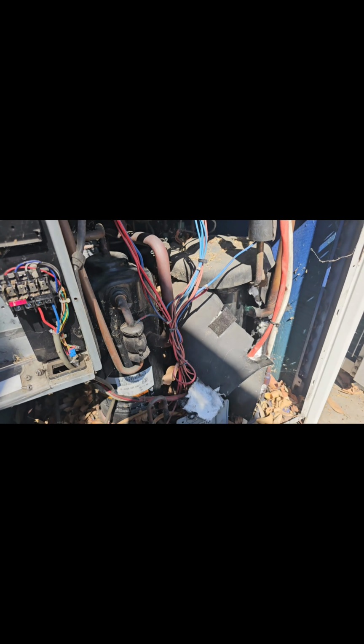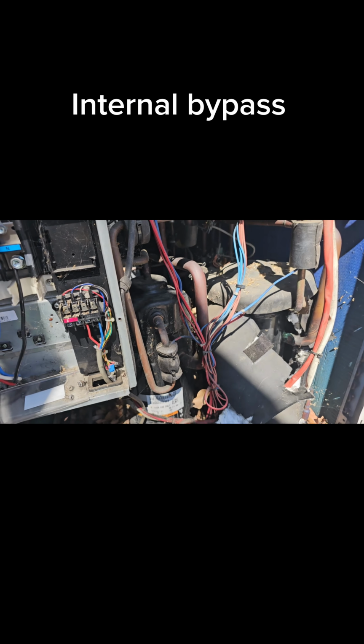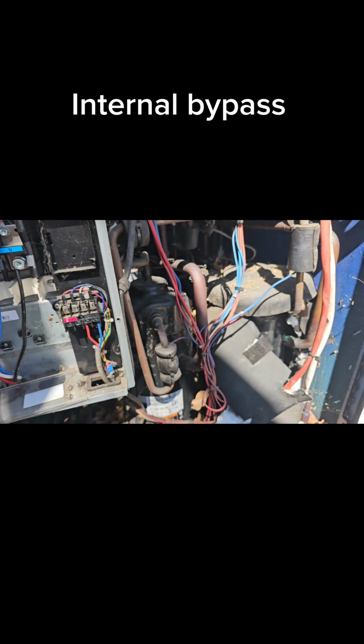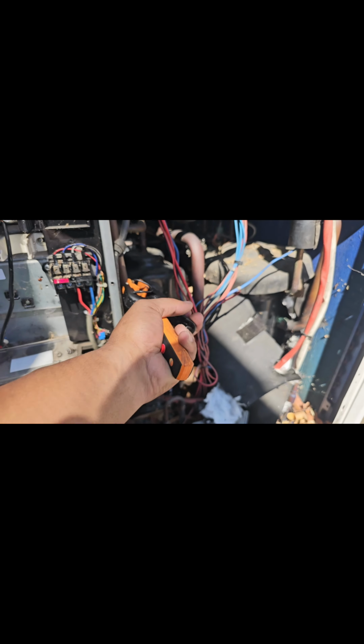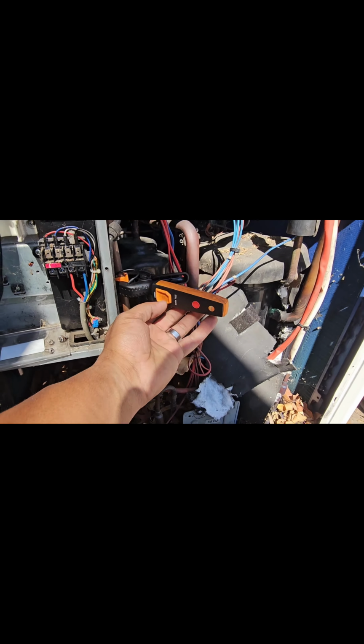Now when compressor 1, which is our digital scroll compressor in our slave module, started up, I could hear that this compressor did not sound very great at all. Because this suction line is extremely hot, it sounds to me that we are bypassing in the shell. So it's running, but essentially, yeah, it's equalized.